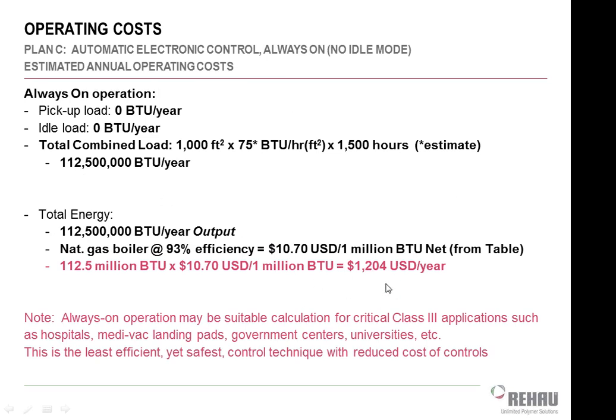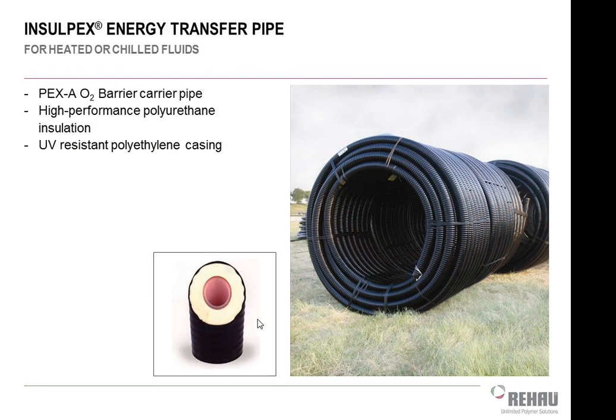We typically use this scenario when we're talking about emergency type facilities, class 3 applications we mentioned a minute ago. We typically use the idling scenario when we're doing regular commercial facilities, like a retail place or something like that, or a parking ramp. And then we typically use the no idle mode for residential facilities, so it only costs you $100, $200 a year to run that. All right, so let's just show you some pictures of that.